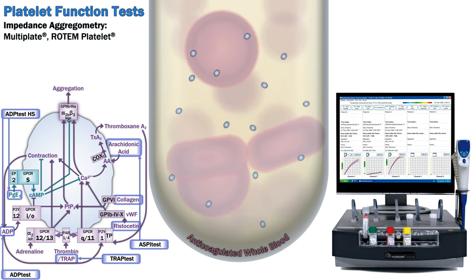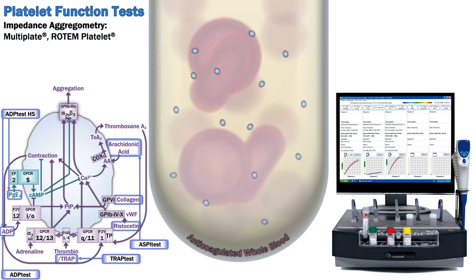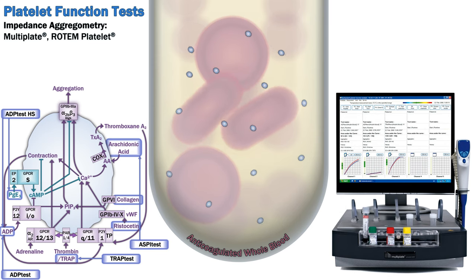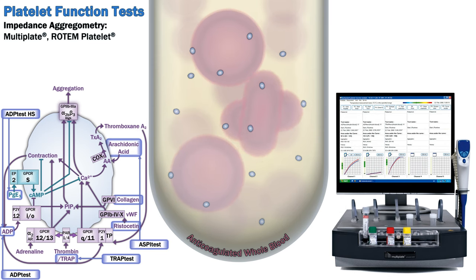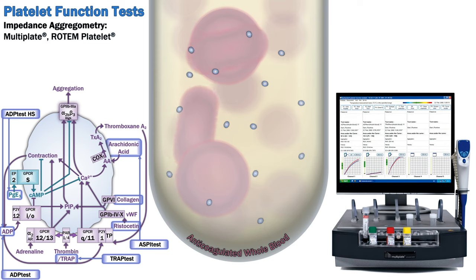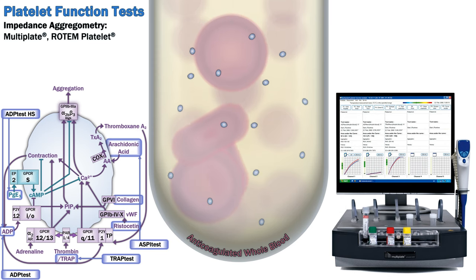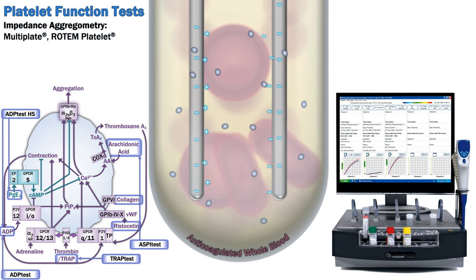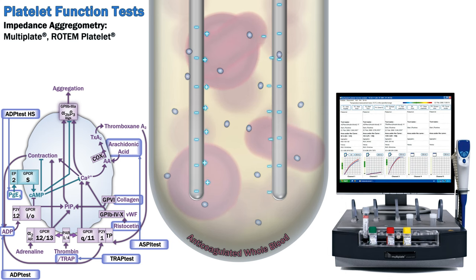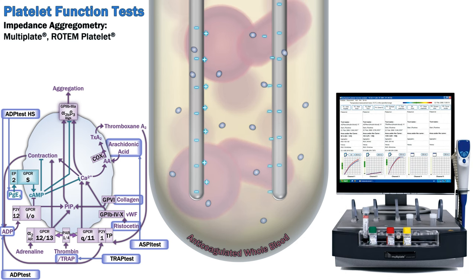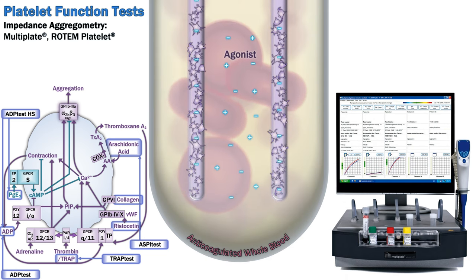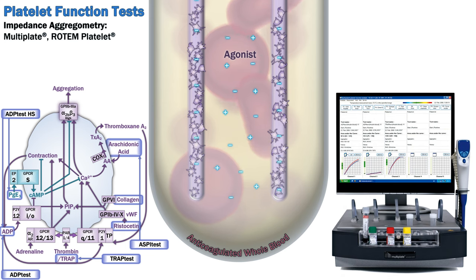Impedance aggregometry is another way to bypass the optical problem with anticoagulated whole blood. It's used in the Multiplate device as well as the platelet function tests packaged with ROTEM. The capabilities of the Multiplate device are significantly closer to the gold standard LTA than VerifyNow — it can use a large variety of agonists and provides continuous output. A pair of electrode wires are placed in the sample and an alternating current is passed through, measuring the impedance over time. When an agonist is added the platelets are stimulated and aggregate on the electrodes, increasing the impedance, which is detected and plotted.